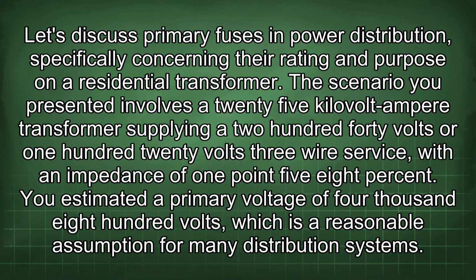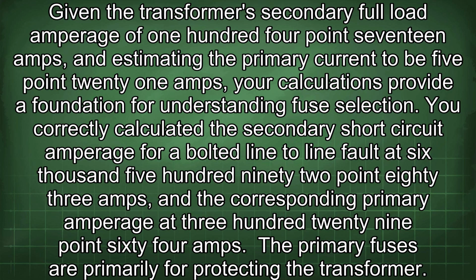Let's discuss primary fuses in power distribution, specifically concerning their rating and purpose on a residential transformer. The scenario you presented involves a 25 kVA transformer supplying a 240 volt or 120 volt 3-wire service with an impedance of 1.58%. You estimated a primary voltage of 4,800 volts, which is a reasonable assumption for many distribution systems. Given the transformer's secondary full load amperage of 104.17 amps, and estimating the primary current to be 5.21 amps, your calculations provide a foundation for understanding fuse selection.